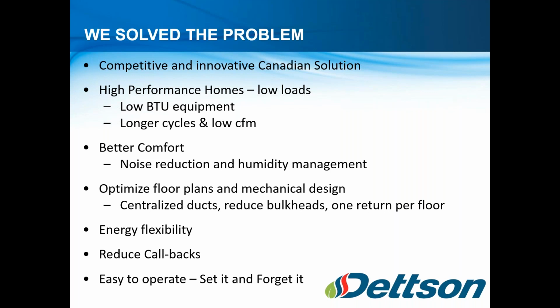Low BTU equipment, longer CFMs, longer cycles, low CFM, driving comfort, noise reduction, humidity management, optimizing those floor plans and mechanical designs, centralizing the ducts, reducing bulkheads and returns, energy flexibility. So we've got a lot of room to play there with an all-electric system, using the heat pump for heating and cooling with a backup gas, or using the heat pump for heating and cooling with electric backup. Actually not backup, shared load. So when the COP on the Alizé hits 1, then the Supreme, the electric furnace, would kick in and work together in a shared load capacity. All around better system, reducing callbacks and warranty issues, and also easy to operate, setting it and forgetting it.